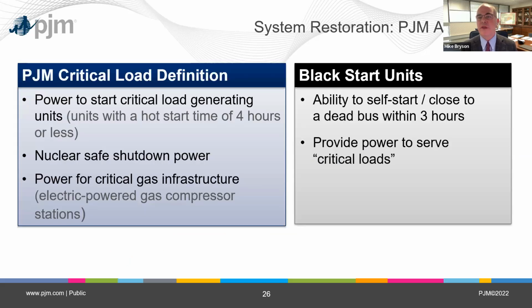I'll talk a little about the PJM approach to deciding how much black start we need. It's really about getting power to bigger units on the system -- we define those units as any units that can start in 4 hours or less. So a black start unit starts with no help, and sets that cranking path to these bigger units that are 4 hours or less away, so we can get those up and running.